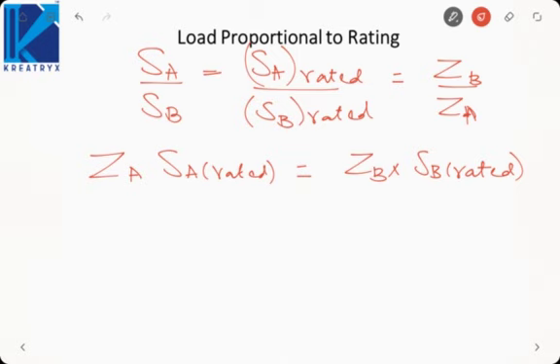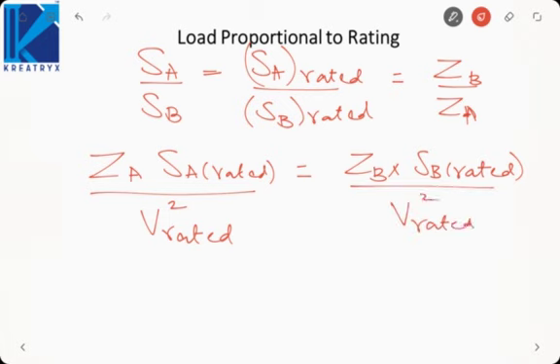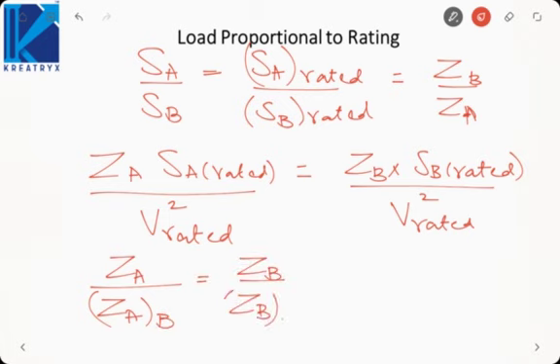Now we know that the rated voltage on both the transformers will be the same. So let us divide it by the rated voltage square, V rated square. Now V square by S will give me Z base. So ZA by ZA base is equal to ZB by ZB base. So ZA in PU will be equal to ZB in PU.